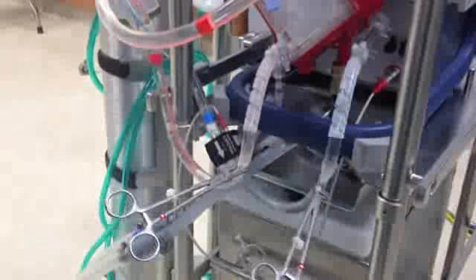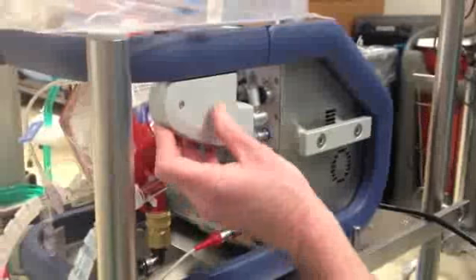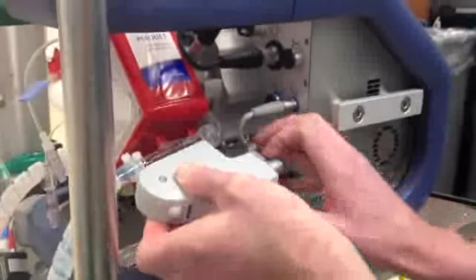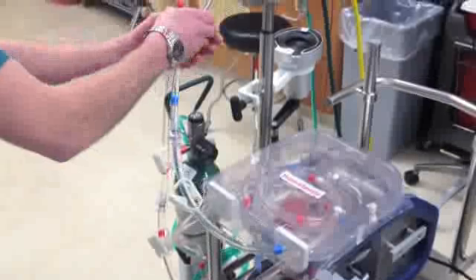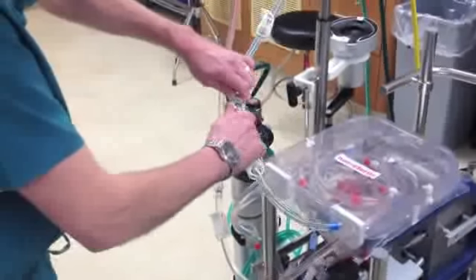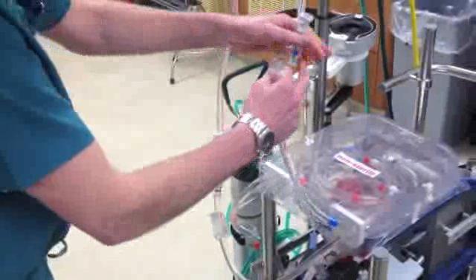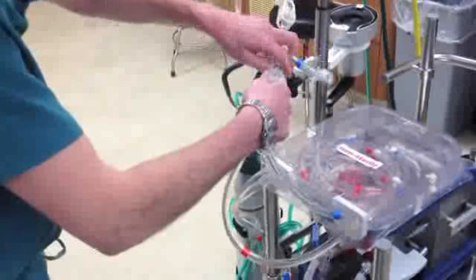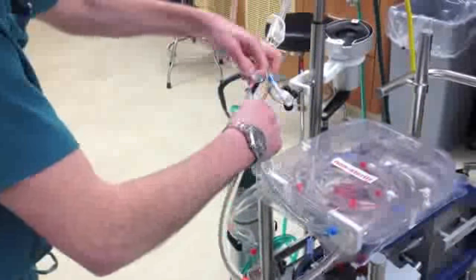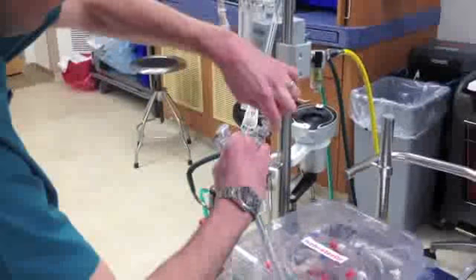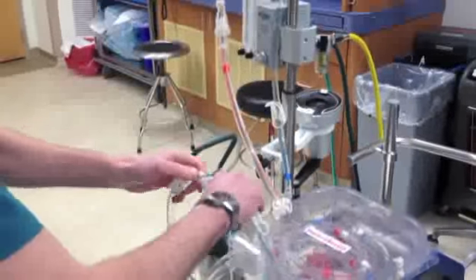Then you'll unclamp your sensor, your flow sensor, and clamp the red and the blue lines that are attached to the HLS set. You'll go to the side and unhook the venous probe and connect it to the HLS set, and then you're ready to clamp off your lines. Those are the priming lines that he's clamping, and the table tray line he just clamped, priming line, and then table tray. And you'll disconnect using the quick connectors there, and you'll essentially complete your circuit here by connecting the red and blue priming lines to each other and the red and blue table set lines to each other, and that will give you a complete circuit that can then be handed off to the sterile field.